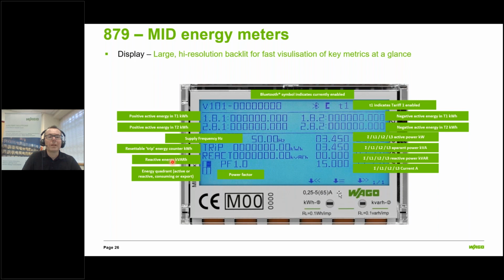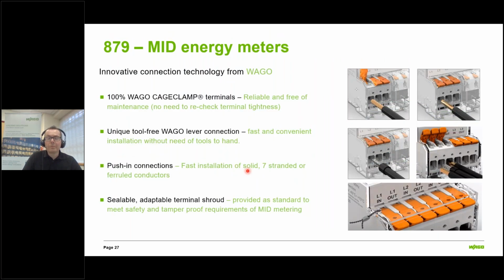Reactive energy, KVAR hours, and then what's known as the energy quadrant, whether it's active or reactive, consuming or exporting. And you've got the four quadrants there. And finally, the power factor, which, if it's at one, is a measure that you have good quality power. Some other benefits of the meters: you have WAGO cage clamp with levers for fast, reliable use with various cable conductor types. For the MID approval, there is a sealable cover to ensure tamper-free operation.